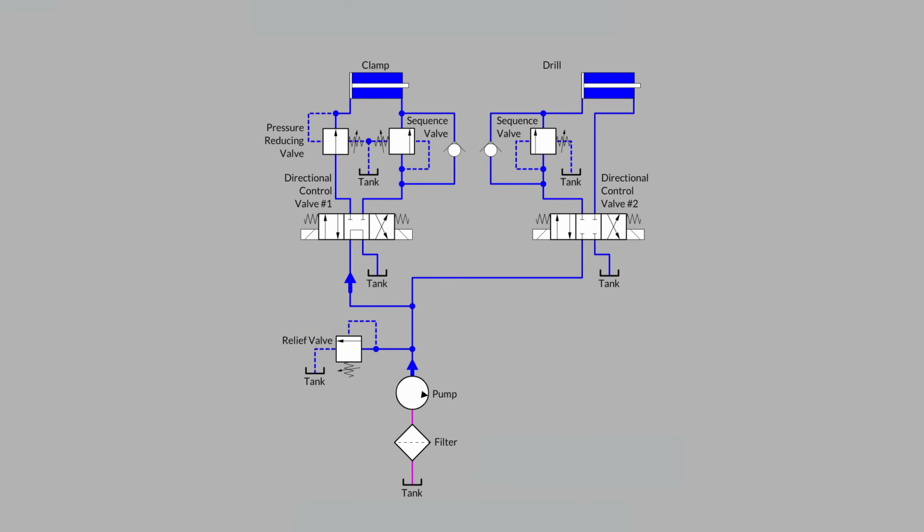Let's get this circuit rolling and let's start to analyze the layout of the schematic and the function of the machine. So notice, of course, that we've got a fixed displacement pump, so the system relief valve is very important, but that the system relief valve is not currently in use. With the directional valves in the neutral position, we find out that the left circuit valve, the directional valve on the left side here, is a tandem center, or sometimes known as P to T connected, and is simply taking our pump's flow back to tank unloaded, keeping our pressure at a minimum level. Over on the right hand side, the directional valve is a closed center valve with the P, T, and A and B work ports blocked when the valve is at neutral.